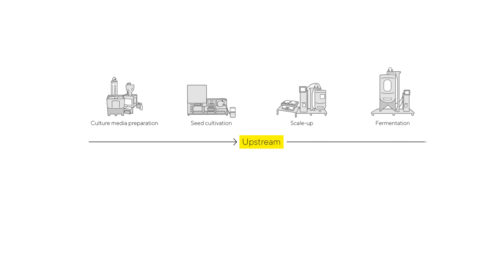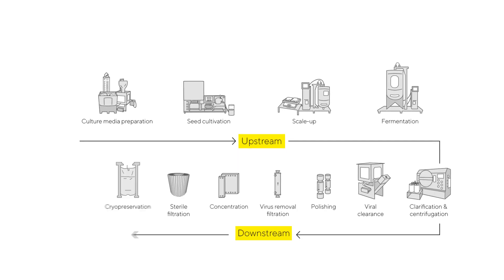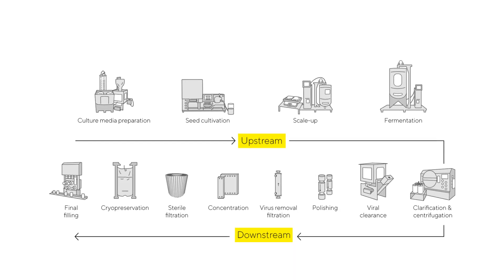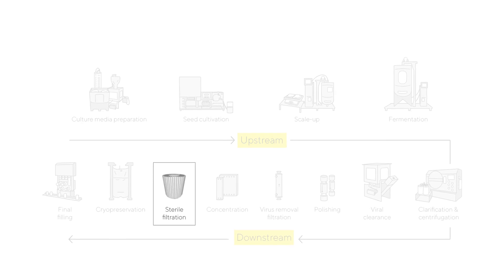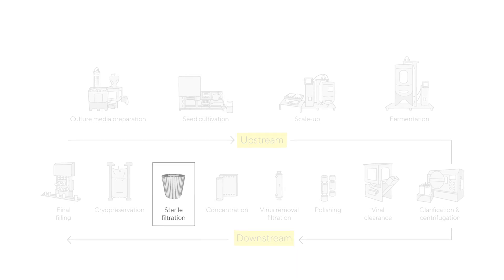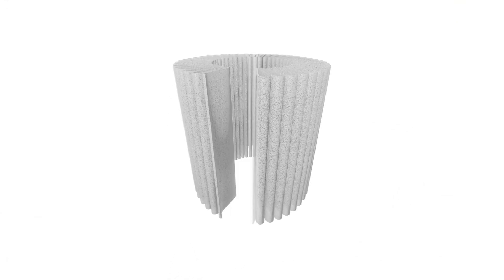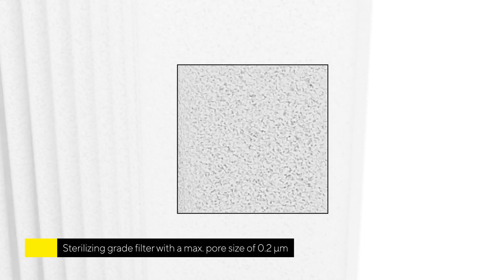Every sterile filtration's goal is the complete removal of microorganisms from the product stream. A sterilising grade filter with a maximum pore size of 0.2 micrometres should be validated to reproducibly remove viable microorganisms from the process stream, producing a sterile effluent, according to the FDA.